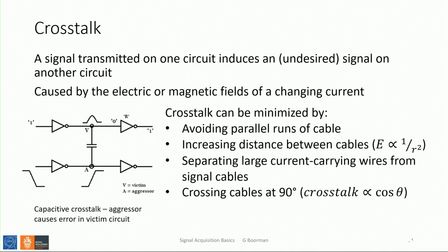How can you avoid all that? Don't put things in parallel - that's always the golden rule. If things do go in parallel, space them apart. The field is inversely proportional to the square of the distance between them. So you don't want high sensitivity thermocouple cables running next to large switching currents on a motor or a high-powered valve or something. Avoid all these issues - keep signal cables well away from power cables.